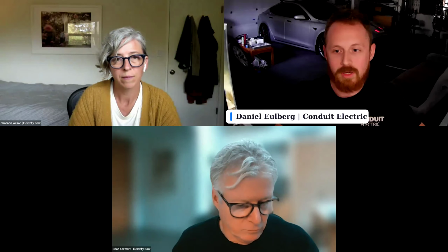Now, the one thing I'll say to qualify this is that you do need to have what's known as a main breaker on your electrical panel in order to make this happen, because without the main breaker, you don't have any way of disconnecting your home electrical system from the grid supplying your home. The picture Brian chose for that interlock kit in his presentation did include a main breaker style panel with an interlock, of course. Not everybody knows if they have a main breaker in their panel - that's the main thing to consider.